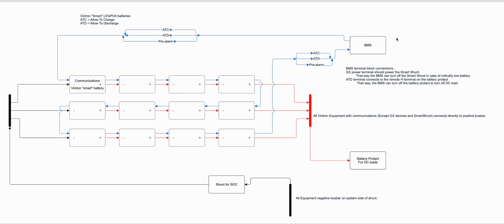Now, if we've got the VE.Bus BMS version 2, then in that case, it tells the GX device, like the Cerbo GX, to stop charging, for example. And then that way the Cerbo GX can then tell the charge controllers to stop charging. And so we've got a really great system there where you don't need to have switches and all this stuff on all of those things. But if you have DC loads that don't receive communication from the Servo, then you do need to have essentially a solid state relay or a Victron Battery Protect.